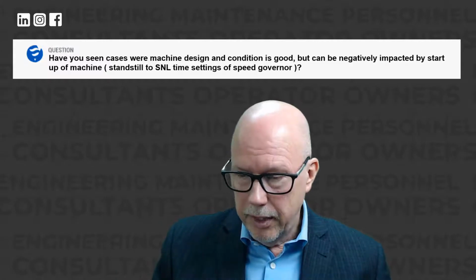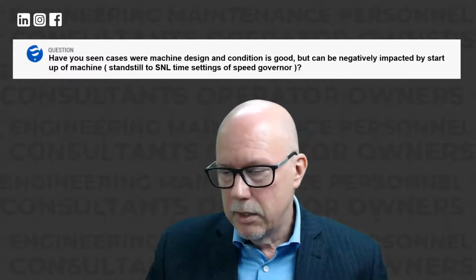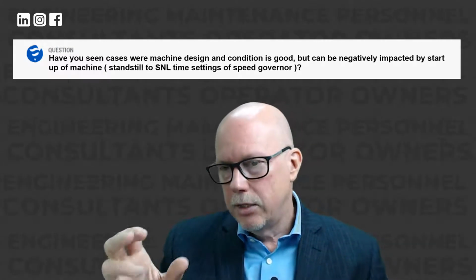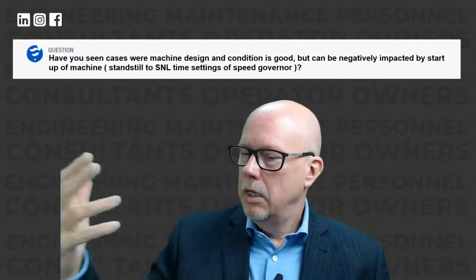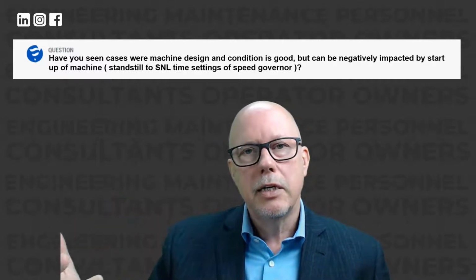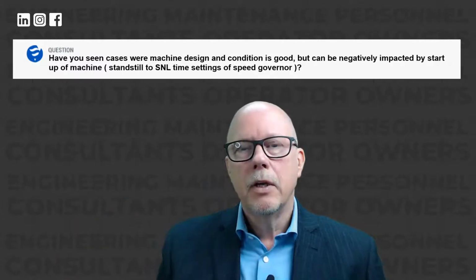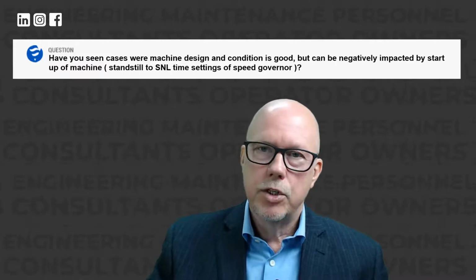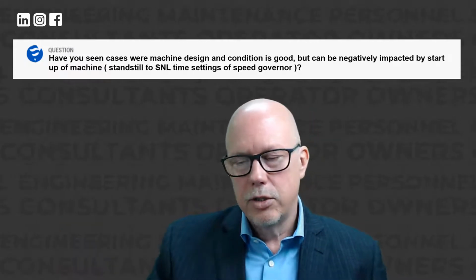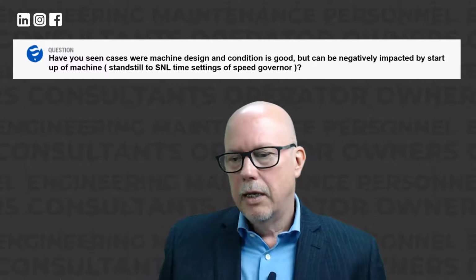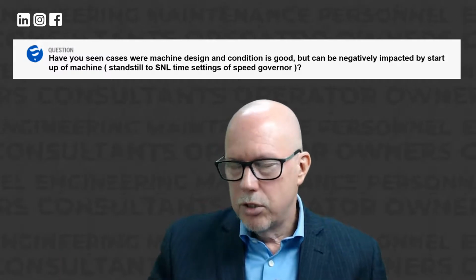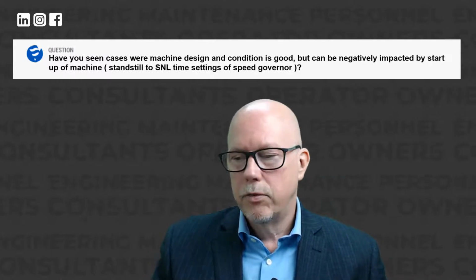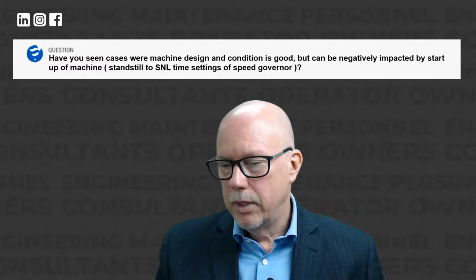So they got the OEM involved, and the OEM was very good. They looked at all the data, contacted us regularly, went back and changed the constraints for the rotor rim, applied corrections, and did the test again, and the unit was fine. So again, use of information at the original commissioning stages to fix issues and make sure these units will work for long periods of time.